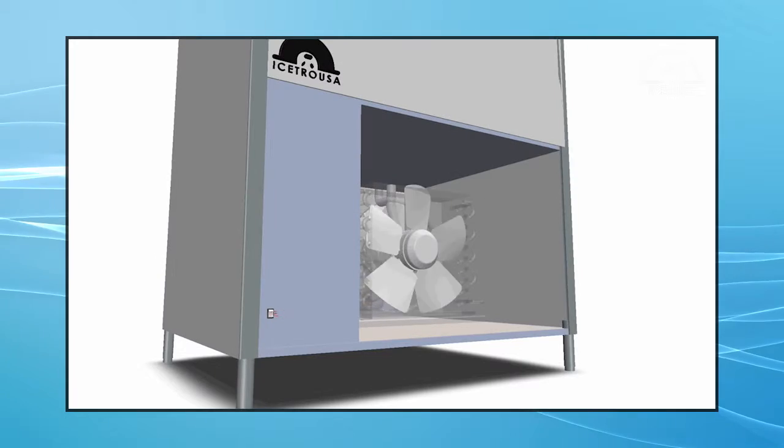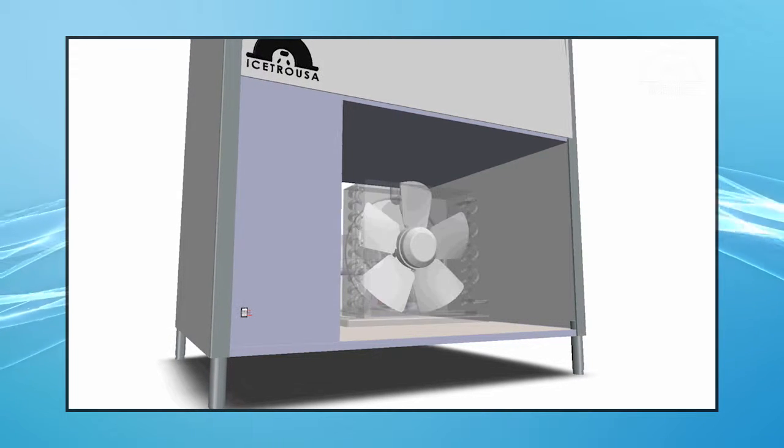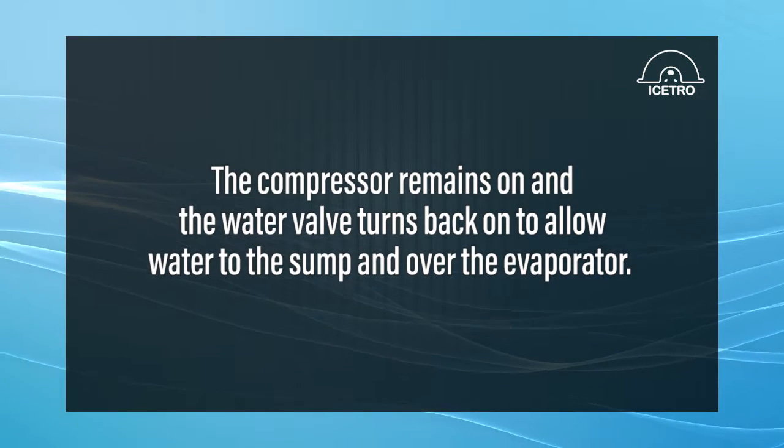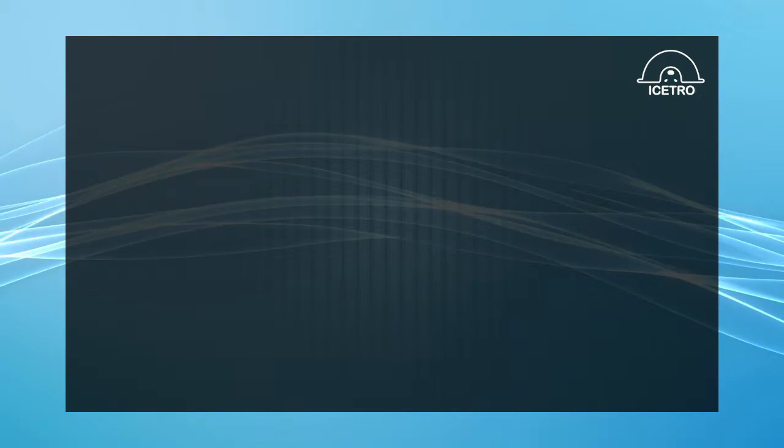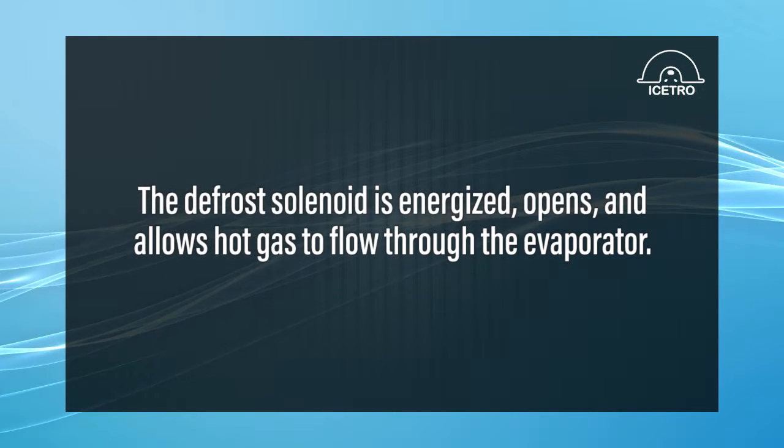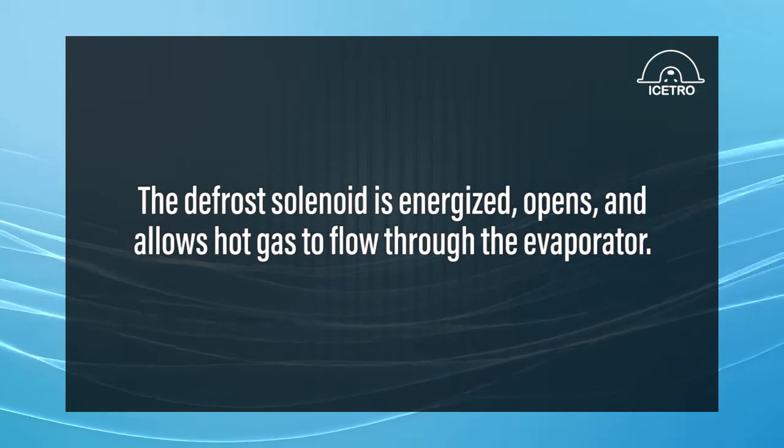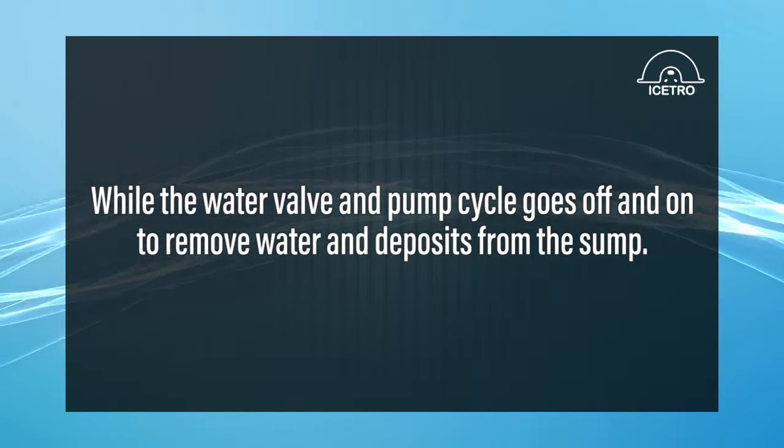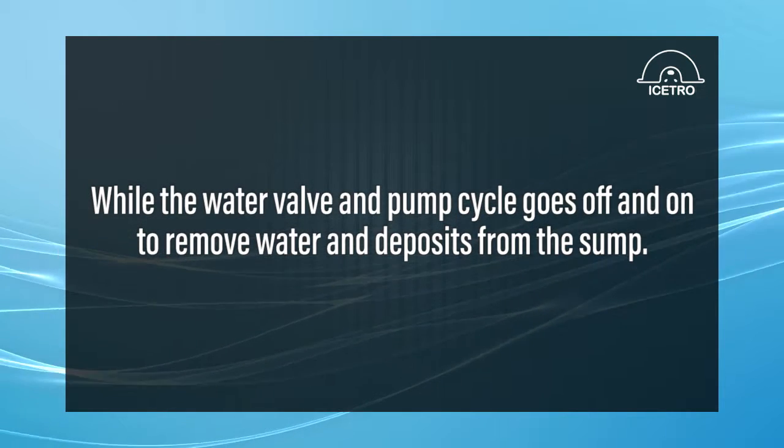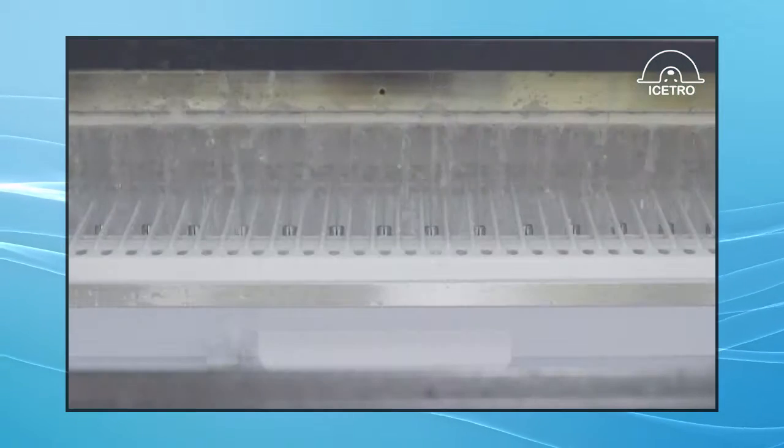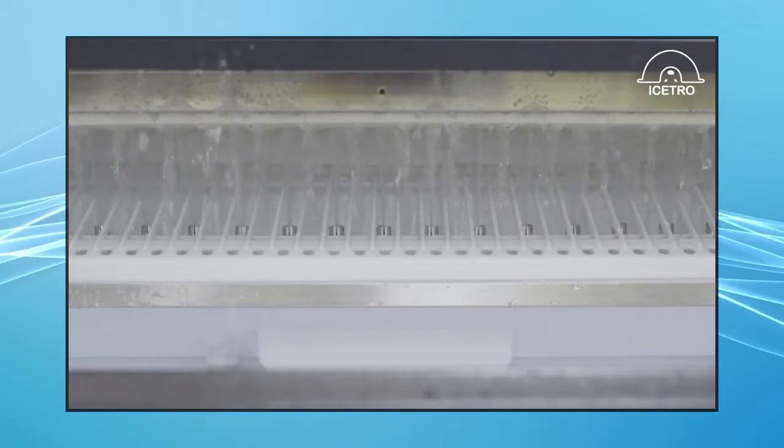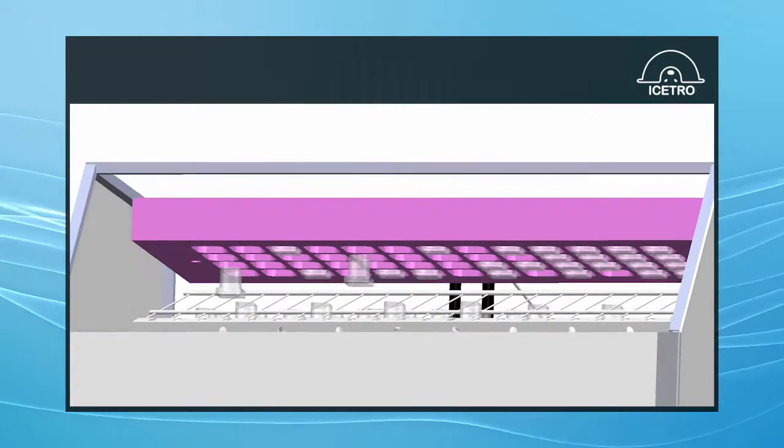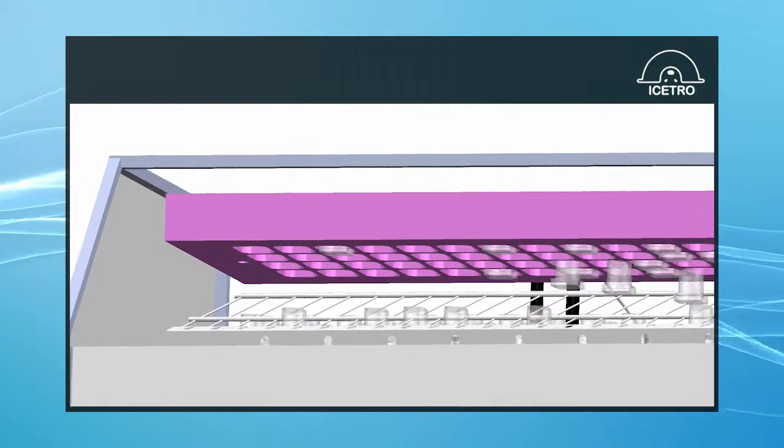After the set time delay has been achieved, the condenser fan motor shuts down. The compressor remains on and the water valve turns back on to allow water to the sump and over the evaporator. And the defrost solenoid is energized and opens and allows hot gas to flow through the evaporator. And while the water valve and pump cycle goes off and on to remove water and deposits from the sump. After a minute and a half, the water pump shuts down. While the water valve remains energized for an additional 50 seconds to fill the sump while hot gas continues to warm the evaporator.